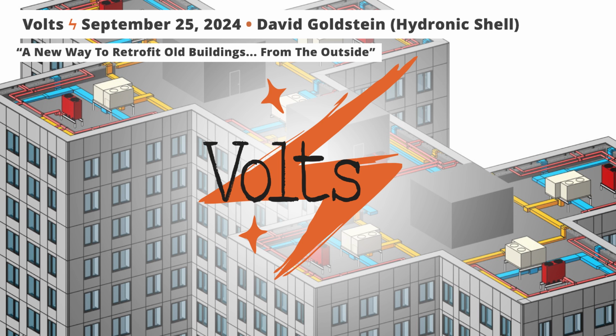Refrigerants are fine for some applications, but there are certainly issues with refrigerants, whether environmental issues or safety issues around flammability. In general, there can be issues when you have refrigerants, especially in larger quantities. When you get to bigger buildings with bigger systems and longer distribution lengths, you're not just distributing 20 feet from an outdoor to an indoor unit, but, if it's a 100-foot tall building, you have much more distribution. So you're talking about much larger quantities of refrigerant, and using refrigerant becomes more and more of a problem. Right. So especially for larger buildings, water really becomes a much more effective way to move the heat around the building. So you have pipes carrying heated and cooled water.